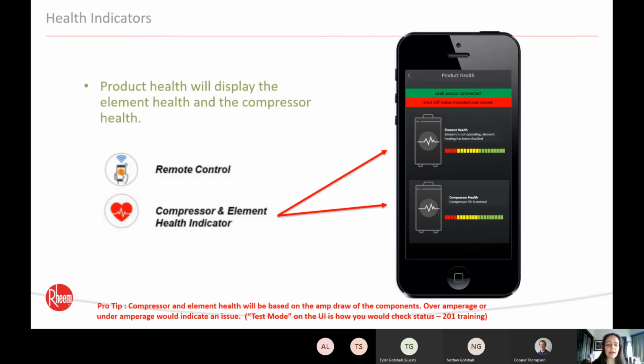We've also added compressor and element health, which is brand new to these 5th generation units. This looks at the amp draw on the components and can let you know if your element health or compressor health is good or bad. There's also a test mode feature, which we'll talk about later, that allows someone servicing the unit to identify specifically which component isn't functioning properly, for a quick turnaround on a service call.